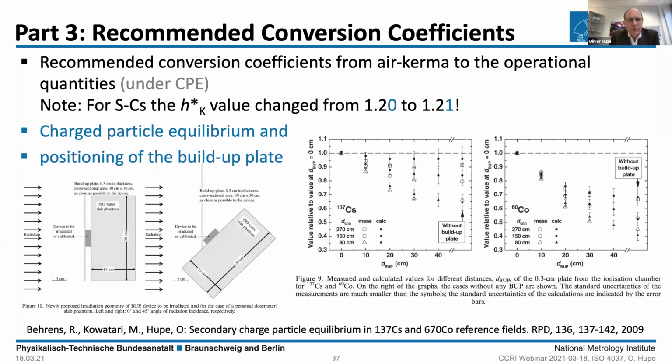The recommended conversion coefficients need charged particle equilibrium, and that depends on the positioning of the build-up plate. There's a publication, we made investigations on this, and we found that if the build-up plate is far away from the dosimeter and you have a dosimeter with a thin entrance window, you don't have charged particle equilibrium, and therefore you have to place it carefully. So this is all published. You can read it on your own.